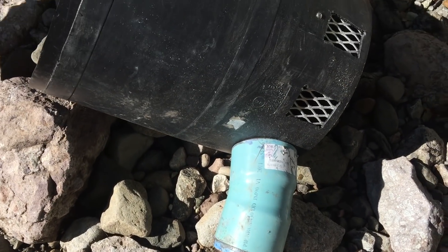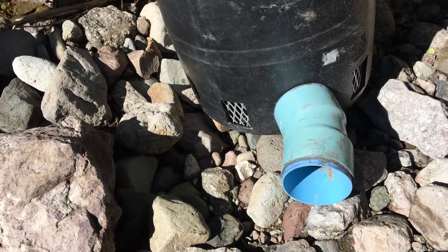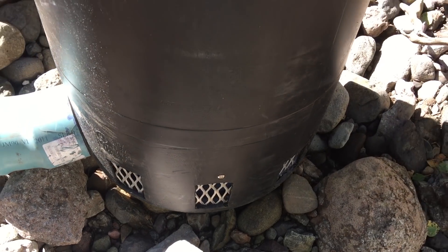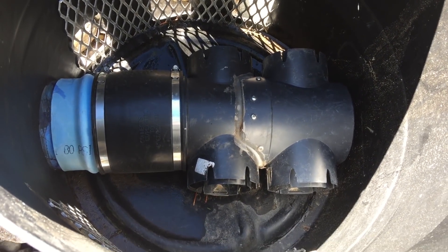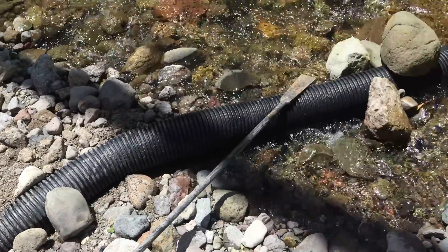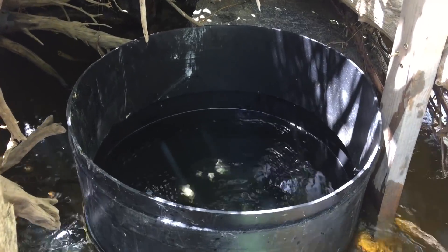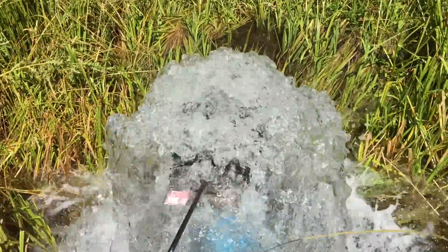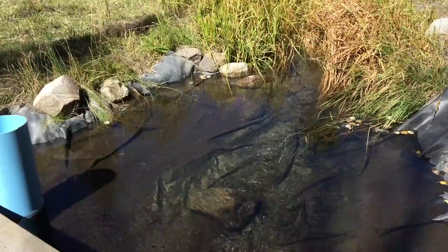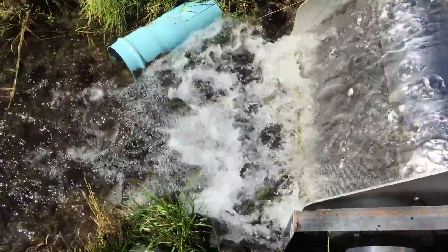This year we are installing a design of intake recommended by one of our viewers — there is a link below which suggested the design. It is constructed from an existing poly drum and spare parts we had laying around. It has screened entry holes all around the bottom to let water into the tank, and a manifold to reduce the potential of vortices. Once we reconfigured the flexible pipeline on the creek bed in the best selected course to maintain rough grade to the intake pool, we installed the intake tank so the intake manifold will always be below the level of the water in the tank. This ensures there will be no air entering or creating an air lock within the flexible pipe. The resulting water we now consistently transport to the meadow is greater than we've ever had, and this, in addition to the better intake screen we've installed, should create the opportunity to potentially add a second jet to our turbine and increase our power in the future.